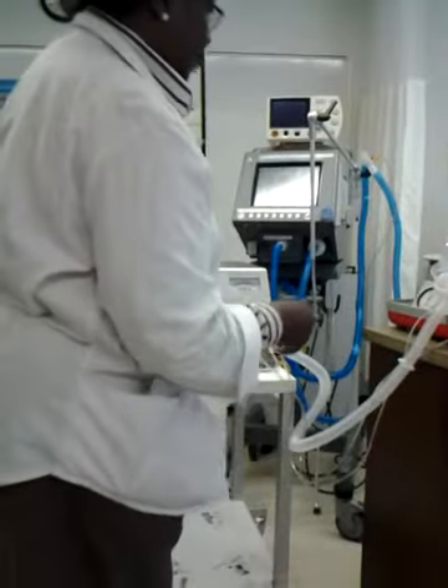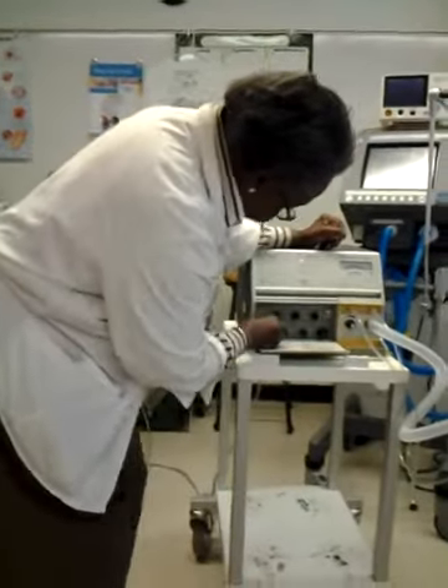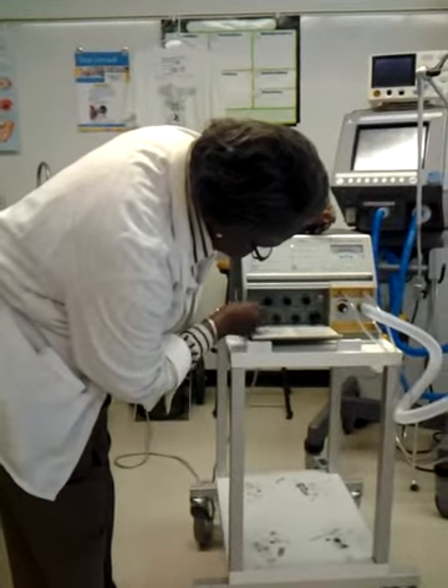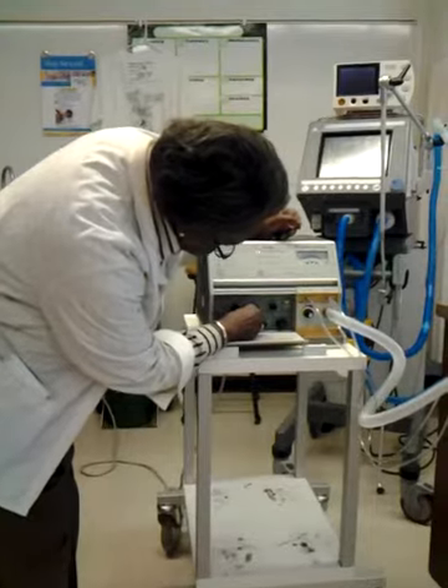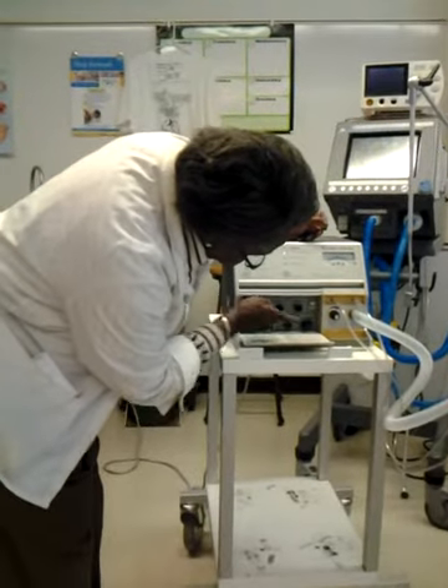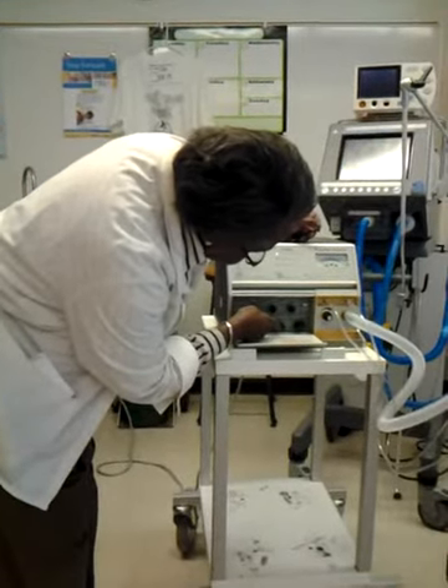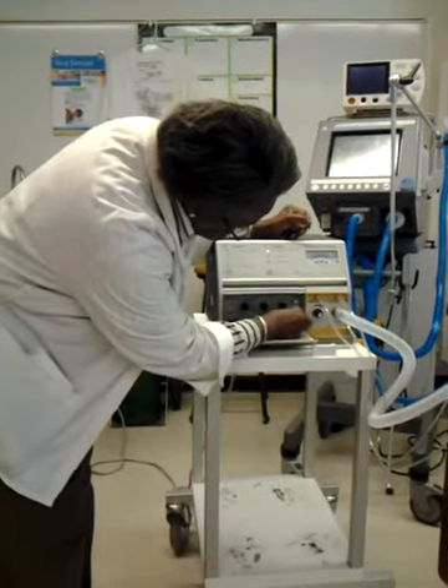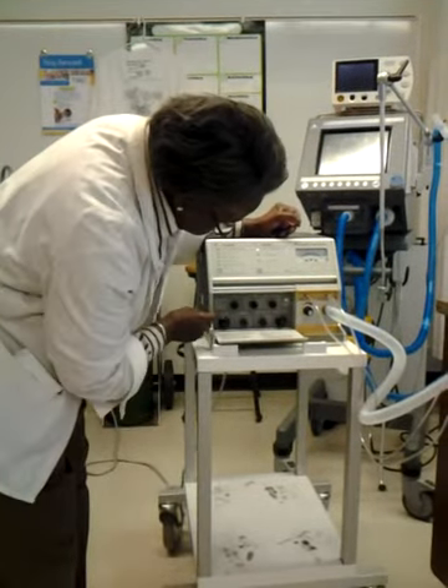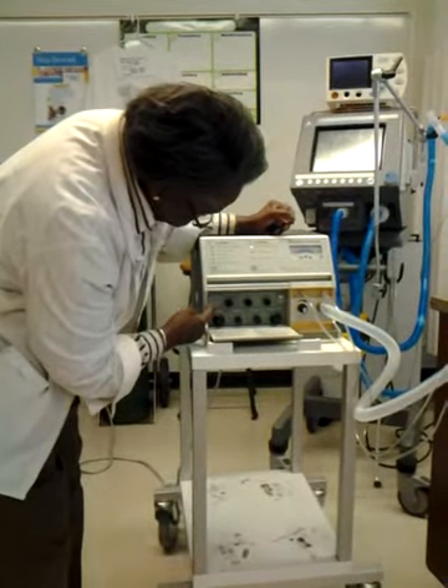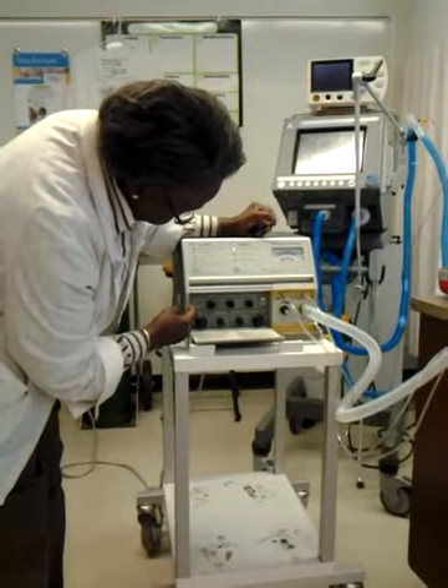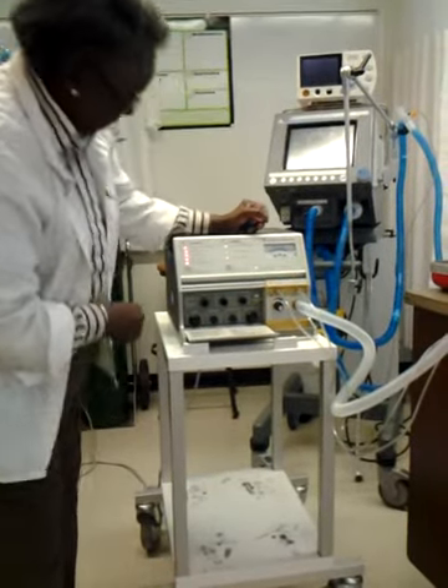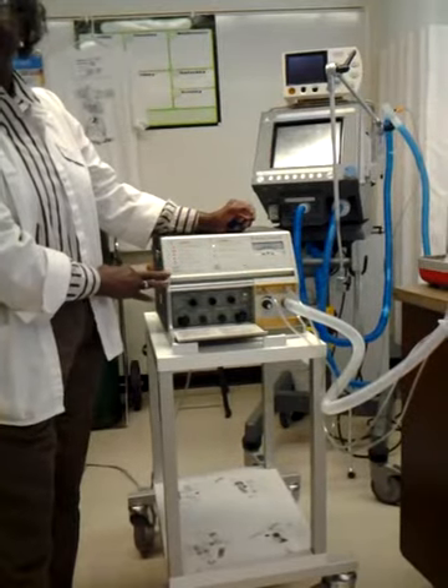So without a PEEP valve here, I can set my tidal volume. I have a tidal volume of 1,000, a respiratory rate of 10 breaths per minute, and my I time set at 1 second. Turn the sensitivity up a little bit, and then in order to turn it on, I just have to go to either assist control or SIMV. If I put my patient in assist control, it goes through the self-test as you saw. It tests its backup battery.